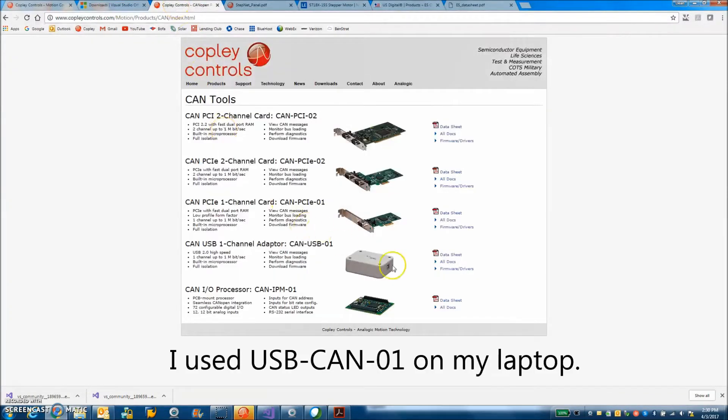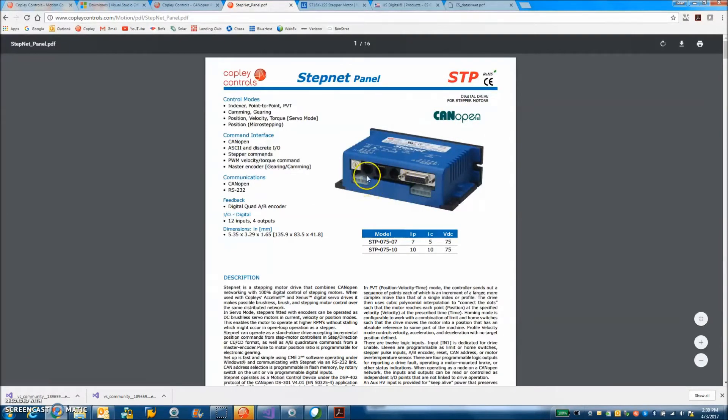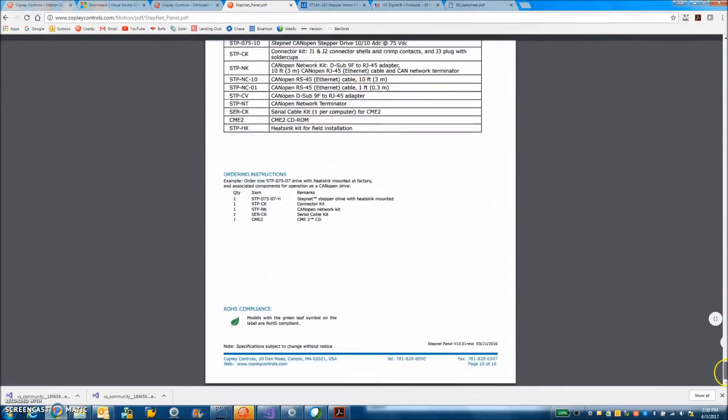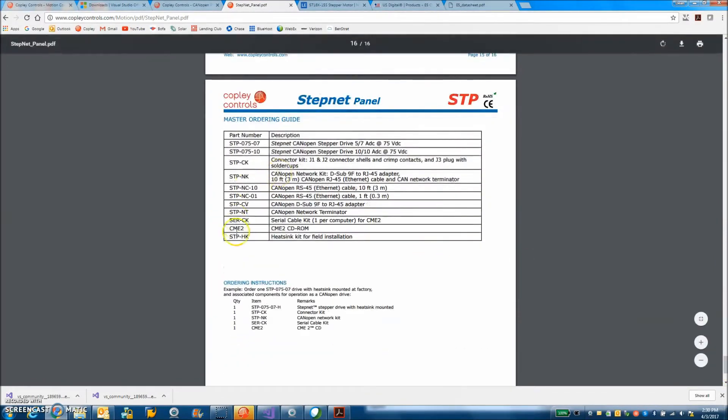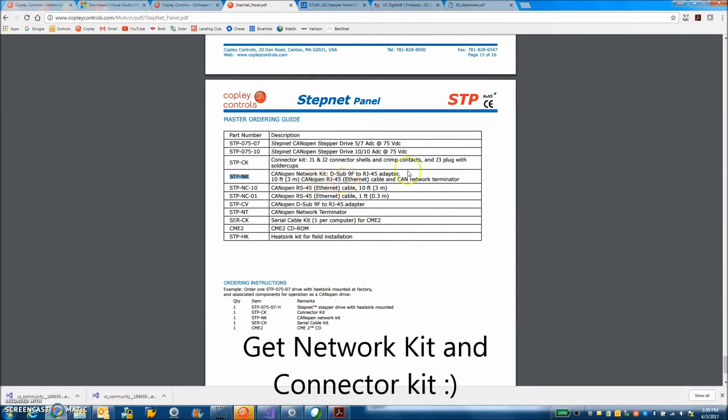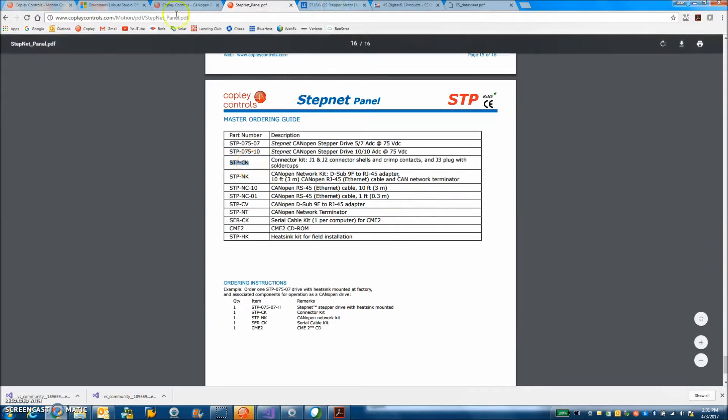So while an install is running we can take a look at what we're going to use to talk to this drive. I've got a StepNet panel here and we're going to get a serial cable connection so we can monitor. We're going to do a CAN connection so we can command it and we'll have a terminator here. On the last page of every data sheet are the accessory items. I'm going to use a USB to RJ11 instead of a serial cable kit. And there's a StepNet NK network kit which comes with the adapter from 9 pin to RJ45 which plugs into the drive and a terminator 120 ohms across CAN high and CAN low.